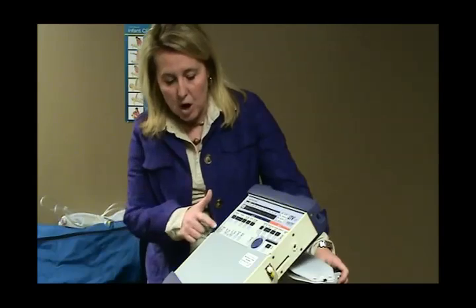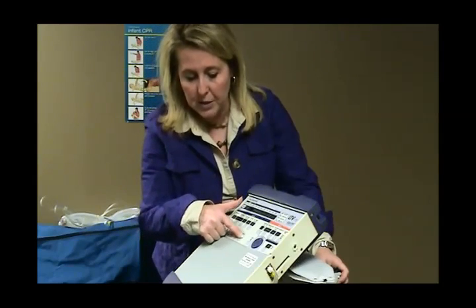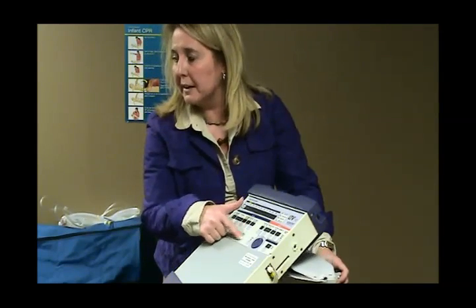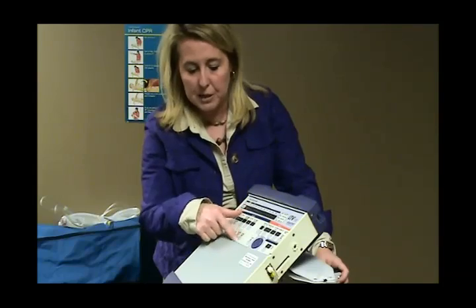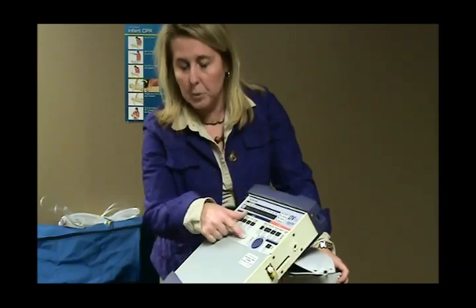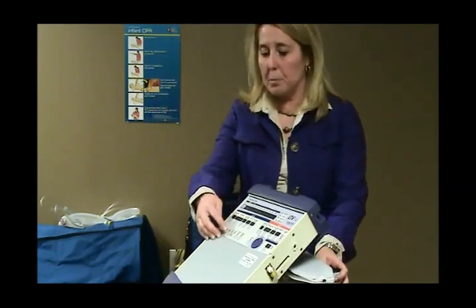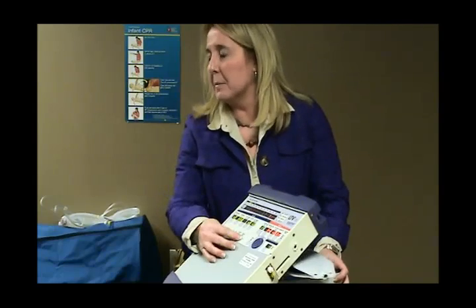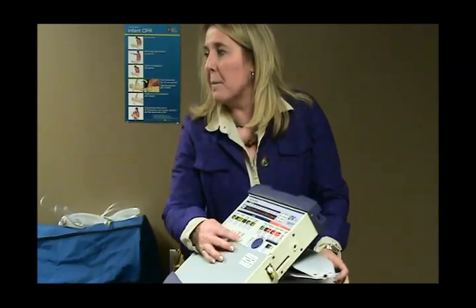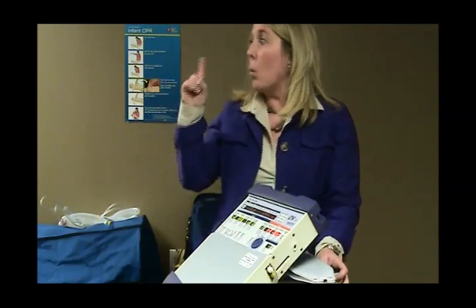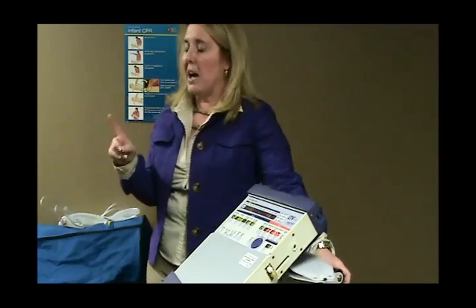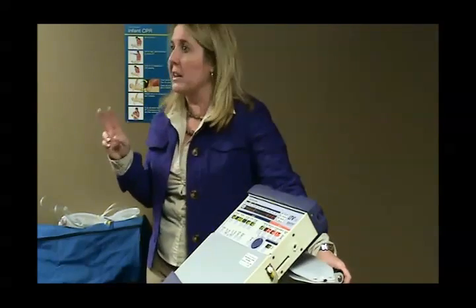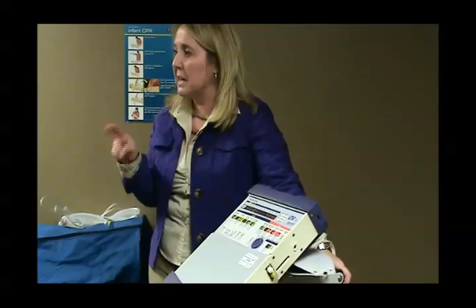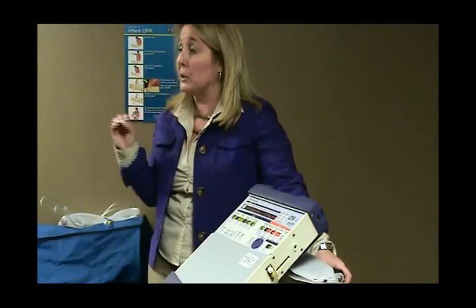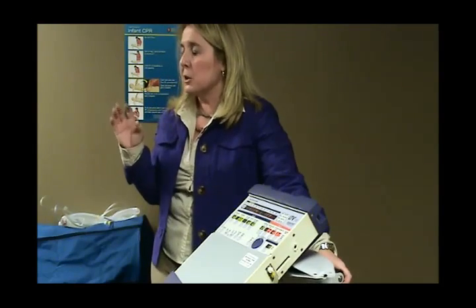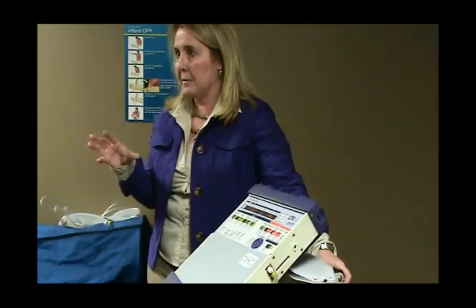The next button across the panel that you need to be familiar with is that manual breath button. It's in the center bottom of the screen. Manual breath. That's your way to bag your patient without disconnecting them. Every time you press that manual breath button, it will give them 1 ventilator breath. Okay, so it won't overventilate them, it won't underventilate them, it gives them just the right amount of ventilation. It will also synchronize with them, so it's much, much, much better than bagging.